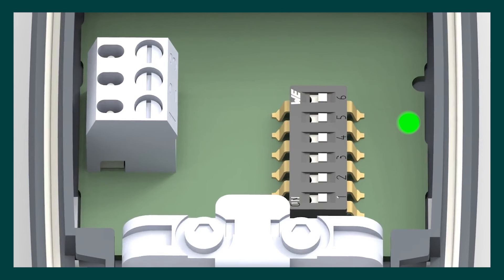Only remove the actuator from the valve in the fully open position. Drive the actuator open with the control signal or by flipping Dipswitch 6 to the on position. Once fully open, turn the power off.